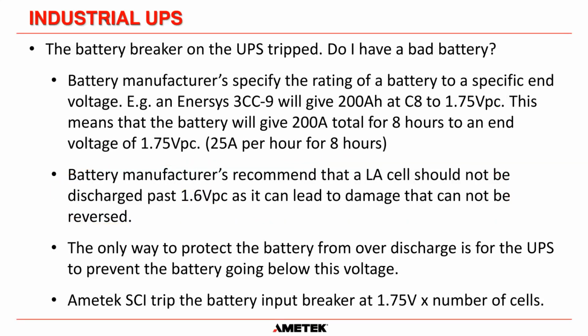Okay, so the only way to protect that battery from over discharge is for the UPS to prevent the battery going below this voltage, and therefore AMETEK SCI have a trip function on the battery input breaker that is set at 1.75 times the number of cells. Now, in most circumstances, for a 120 volt nominal DC system, that is going to be 60 cells.